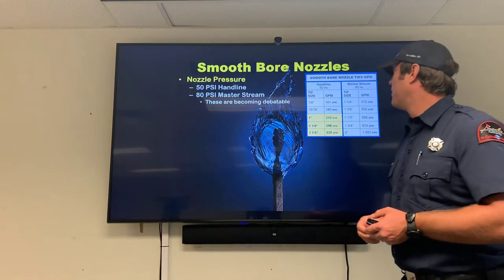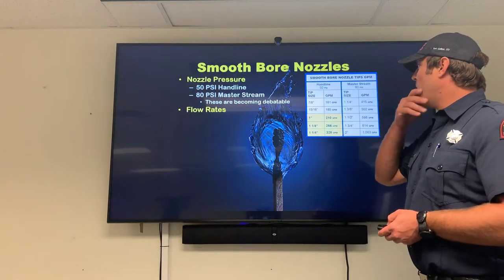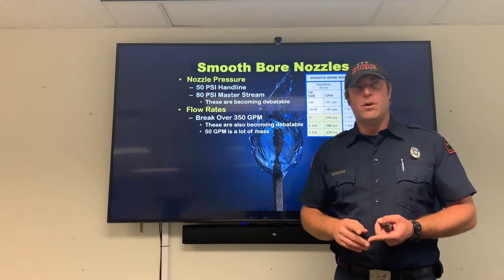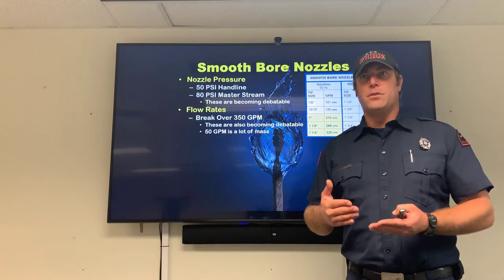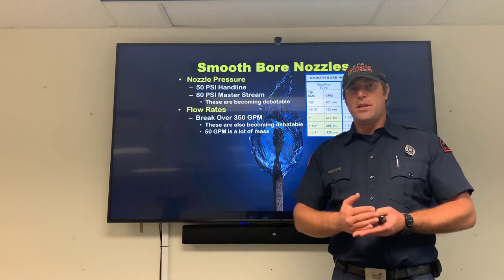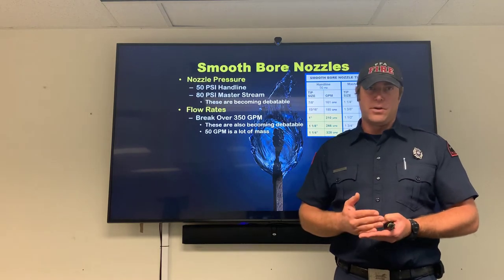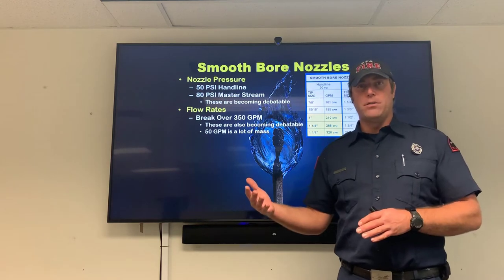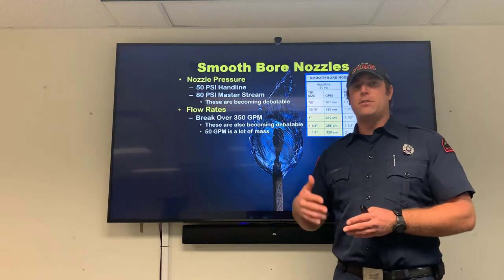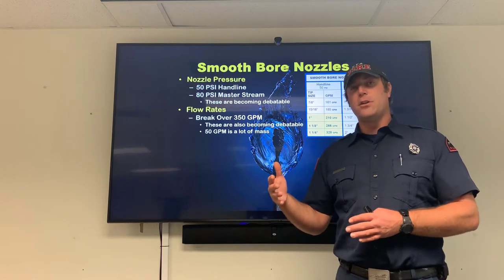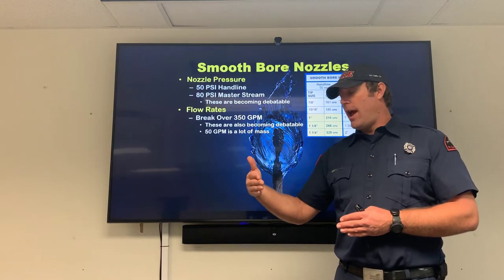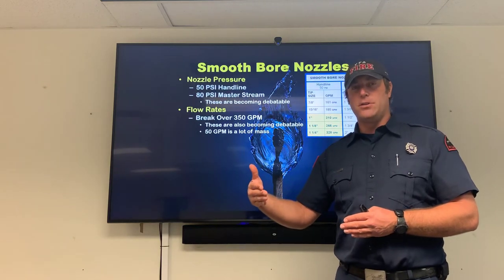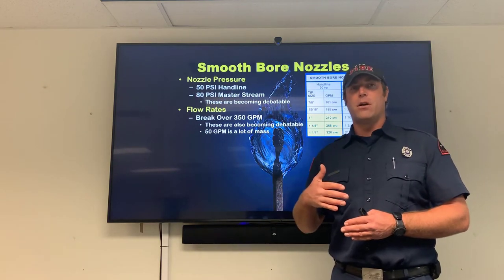Flow rates for smoothbore nozzles are dictated by nozzle pressure: put 50 pounds on an inch-and-an-eighth tip and you get exactly 266 GPM. That's so consistent that we use it to calibrate flow meters — during pump tests or flow tests we'll put an inch-and-an-eighth tip, pilot it at exactly 50 PSI, and if we get exactly 266 GPM we know our flow meter is functioning correctly.